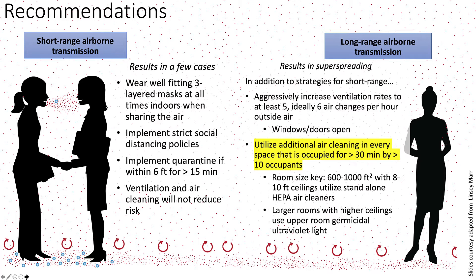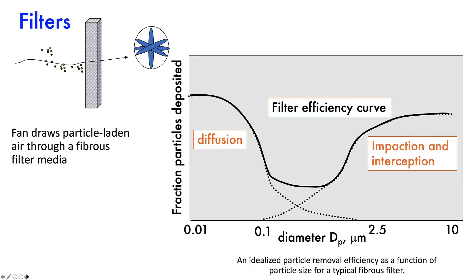Make sure that you can provide the right size air cleaner for the room in which you are applying it. A fan will draw particle-laden air through a fiber filter media. Very small particles deposit in the filter by diffusion, and very large particles deposit by impaction and interception. These combined create the filter efficiency curve where the minimum efficiency is at 0.3 microns.